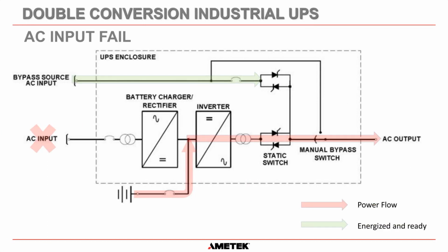Now, this diagram here shows you what happens if we have an AC input power fail. So what you will find is in most well-designed systems, the AC input will come from one MCC and the bypass source input will come from another MCC to give you some redundancy. So in this example, what we're saying is, let's say that the MCC that feeds this AC input here has been taken down for maintenance or has had a failure and the MCC has had to be completely shut down. Let's say the transformer feeding the MCC has failed or something like that.